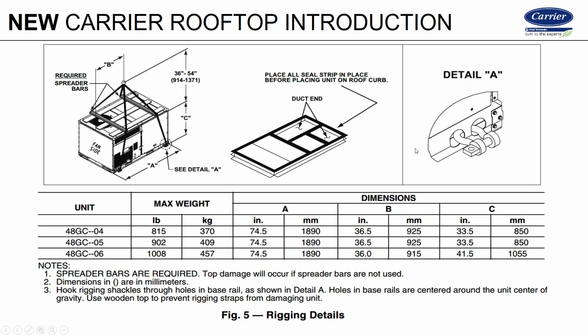Jeff Boucher points out a tip, and Jeff's up in Minnesota, so it's probably easy for him. But in the wintertime, it's pretty easy to spot some of these units that are not held tight because the air leaking out of those gaps is actually melting the snow in that specific spot. Yep, exactly. It'll be dry and warm, or it's a nice place to cool off in the summer. But yeah, good point, Jeff.